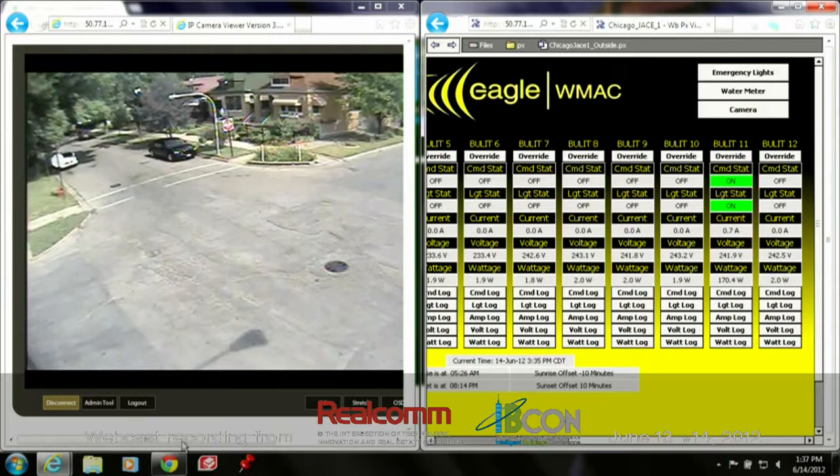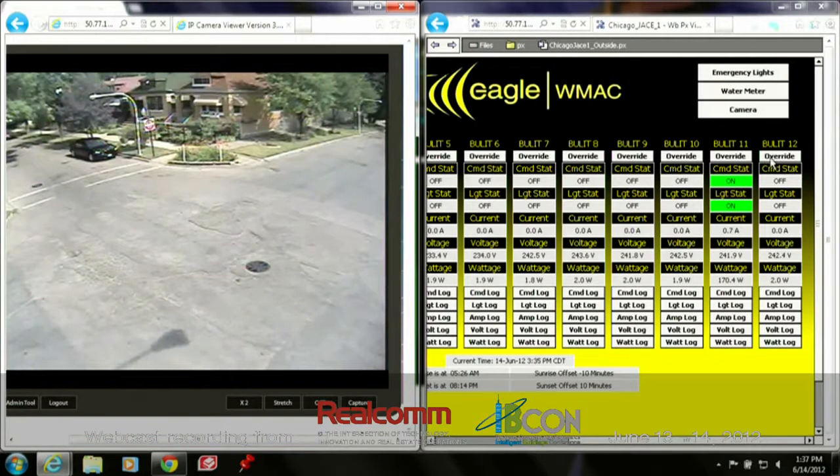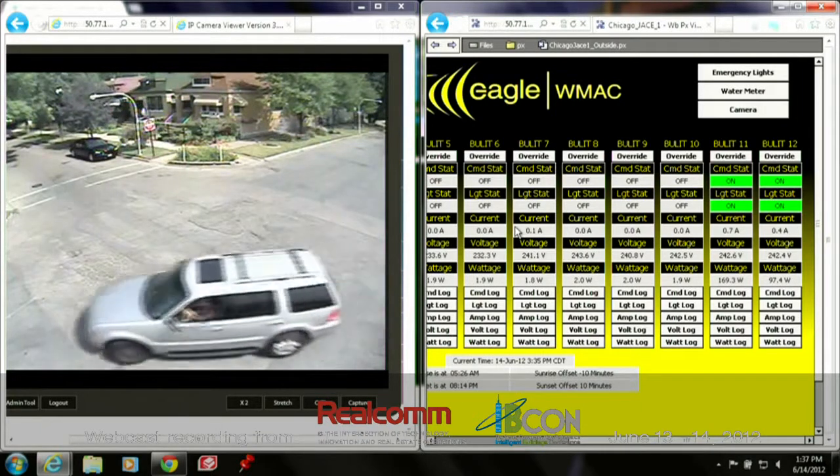Just to speed up the demonstration, I'm going to slide the camera over just a little bit and we'll go ahead and turn on this one as well, so we'll have two lights. These are all being commanded in real time using this Bullet and the Sedona language, which is on the Niagara framework. This site actually has a Tridium JACE mounted on a street pole that's a half mile away from the local area network. We're using our wireless Ethernet radio to communicate that data, and then wireless Sedona to command the lights.